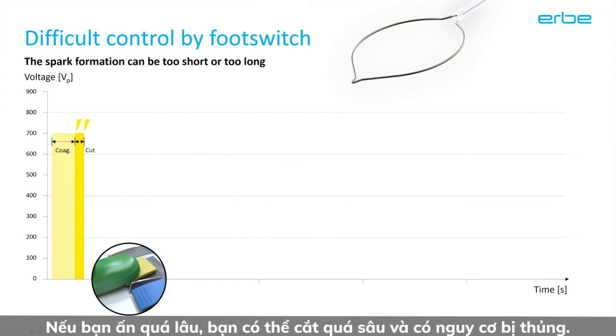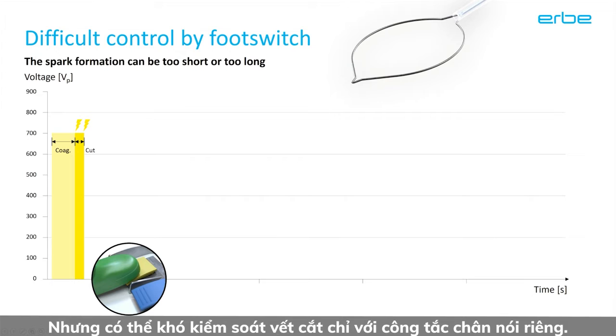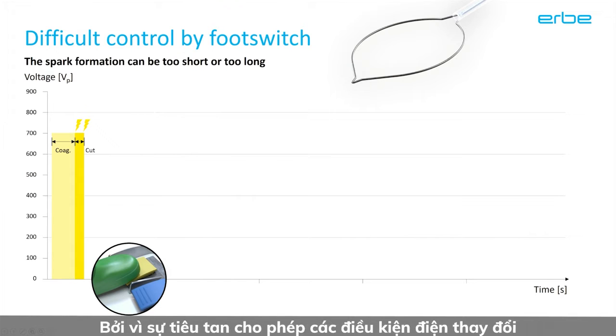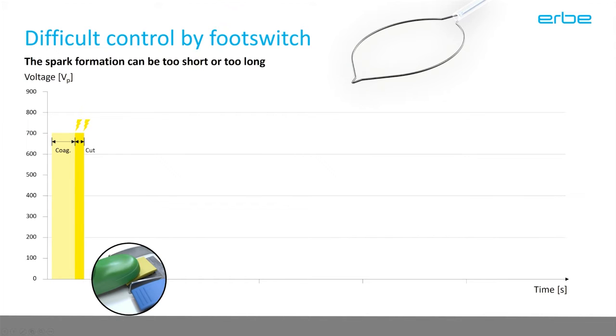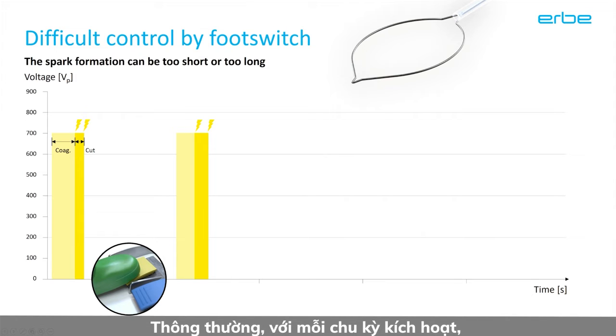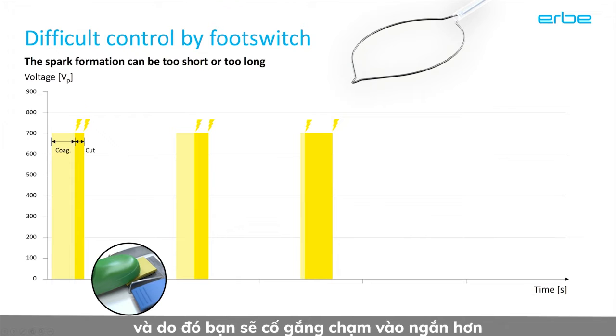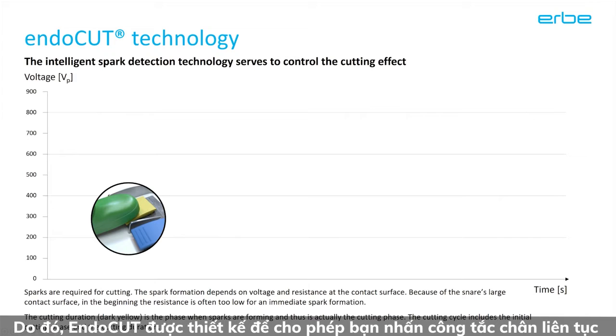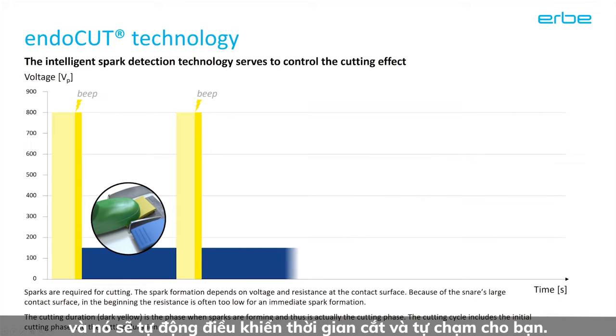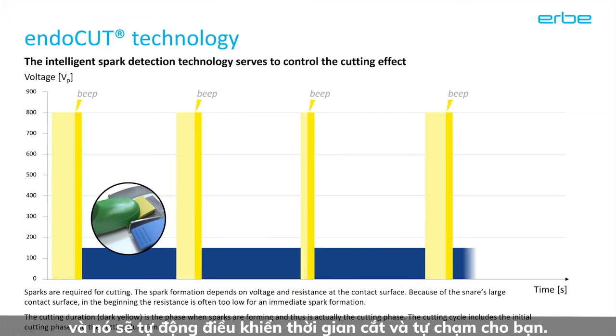If you press too long, you might cut too deep and risk a perforation. But it can be difficult to carefully control the cut just with a foot switch. In particular, because the desiccation lets the electrical conditions change during the procedure. Typically, with every activation cycle, the sparks develop sooner and sooner, and you will therefore try to tap shorter and shorter to prevent that the cut becomes too sharp. Therefore, the EndoCut is designed to let you press the foot switch continuously, and it automatically controls the cutting duration and the tapping for you.